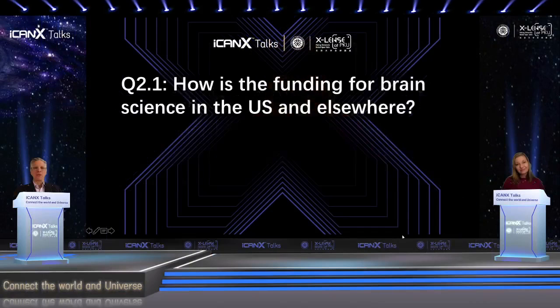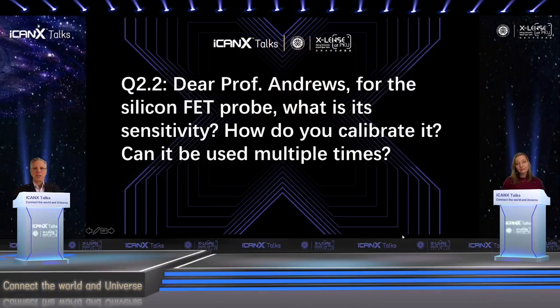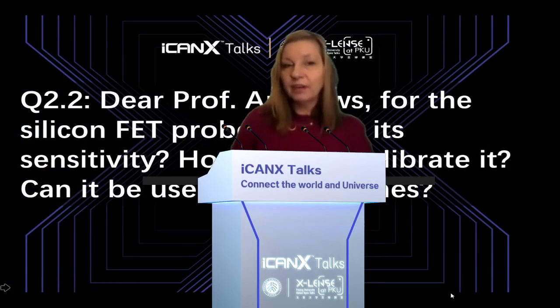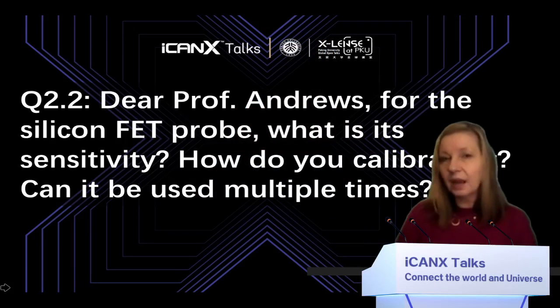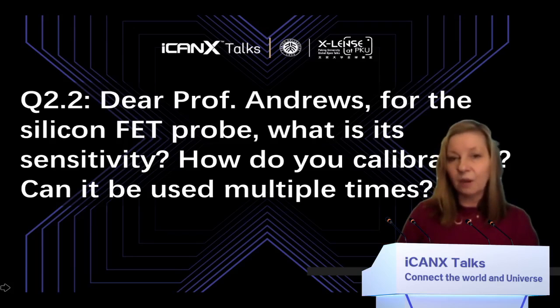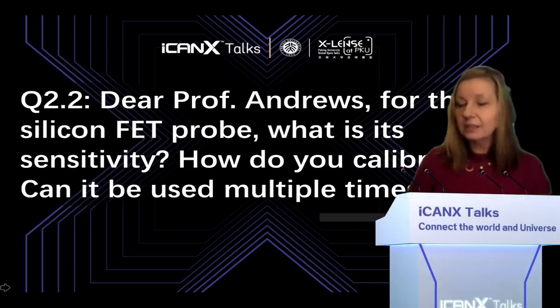Dear Professor Andrews, for the silicon FET probe, what is its sensitivity? How do you calibrate it? And can it be used multiple times? Those are great questions. The sensitivity of those probes is very similar to the sensitivity of the larger FETs. The FETs that we were using for the characterization measurements are about 2 millimeters by 2 millimeters. The FETs on the neuroprobes are as small as 50 microns or 100 microns on a side. But it turns out that sensitivity doesn't scale linearly for field effect transistors, so making them smaller hasn't really impacted our sensitivity. So that still remains good.